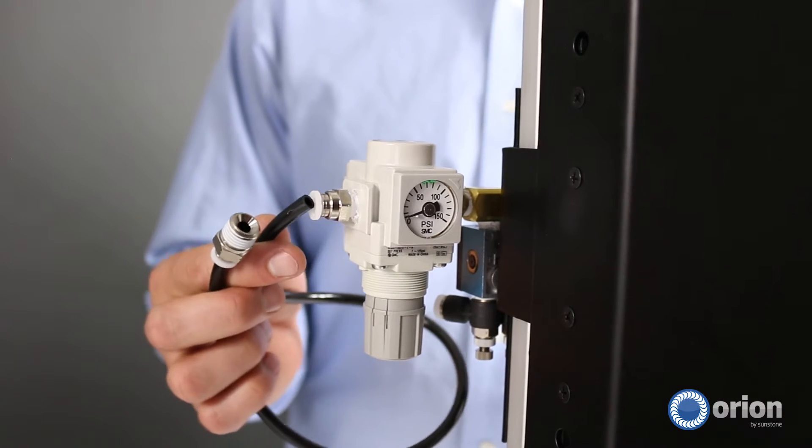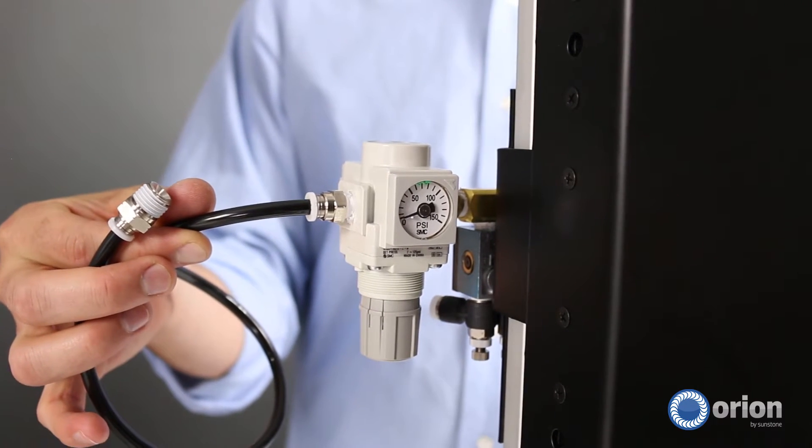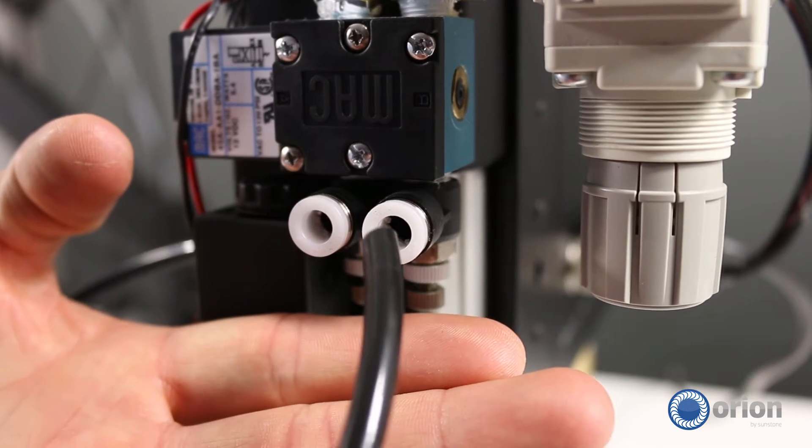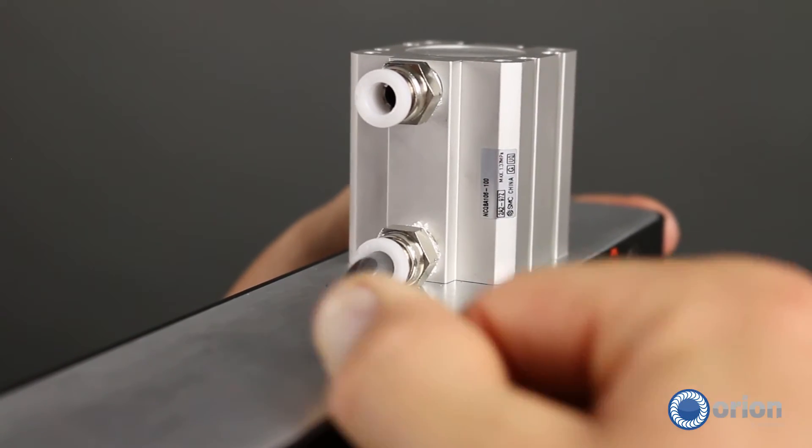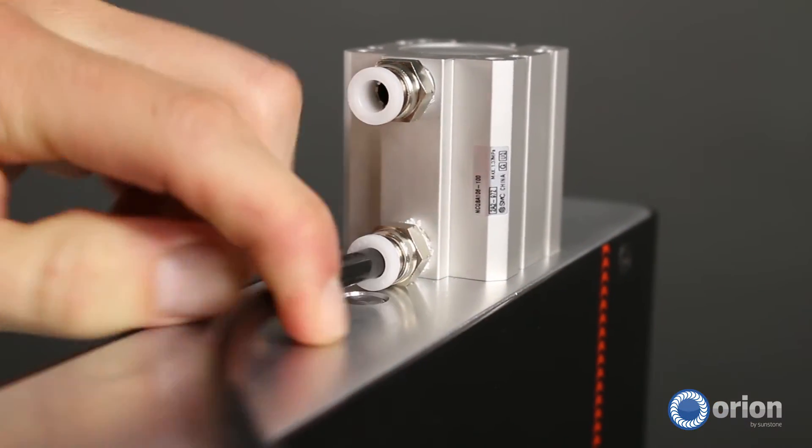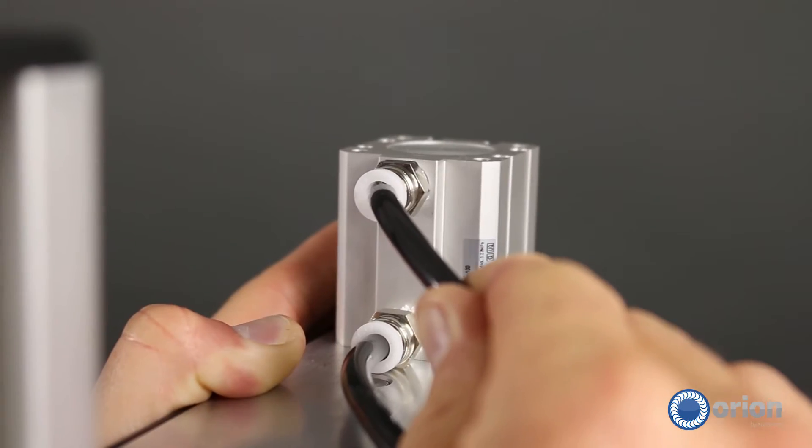Plug the tube from the compressed air tank into the air valve system on the back of the weld head. The right port on the back of the weld head connects to the bottom port on the top of the weld head. The left port on the back of the weld head connects to the upper port on the top of the weld head.